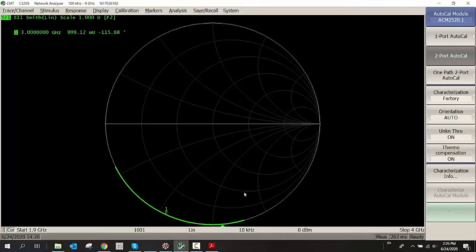I could also verify this real quickly by attaching an open and then going to the Smith chart. I happen to know what this open should look like so I can verify that the calibration is correct. S11 Smith chart and if I go to 3 GHz that is the 115 degrees is correct for this open. It has to do with the internal delay of the open.